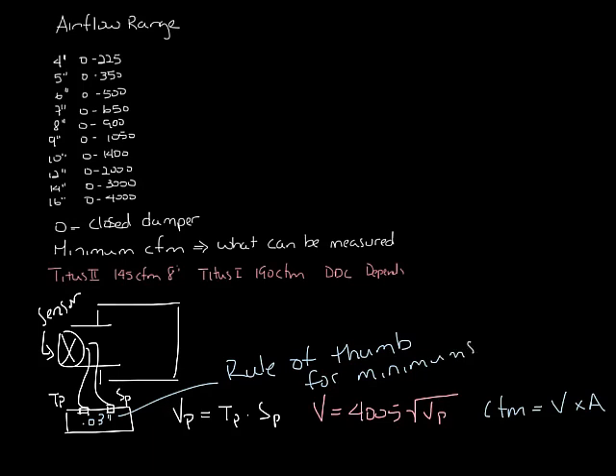If you do that, then you'll get for a 4-inch 45 CFM, 5-inch 65, 6-inch 80, 7-inch 105, 8-inch 145, 9-inch 175, 10-inch 230, 12-inch 325, 14-inch 450, and 16-inch 580. Since this is dependent on the controller you use, you may be able to go higher or lower with your minimums depending on the manufacturer of your controller.